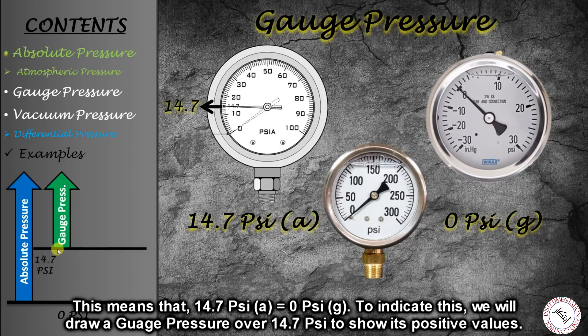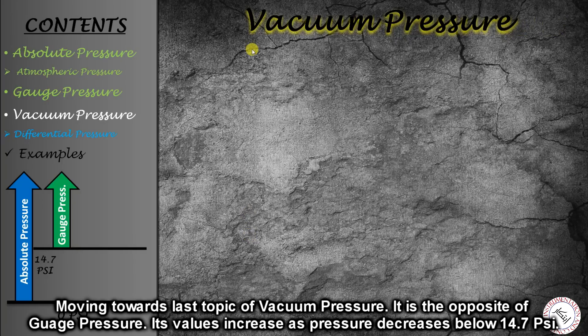If we draw a comparison graph, gauge pressure starts from 0 psi at the 14.7 psi absolute level, and goes in positive values upward. Below 14.7 psi absolute, gauge pressure goes into negative values. Now we introduce the third and last pressure measurement scale: vacuum pressure. Vacuum pressure is totally opposite to gauge pressure — starting from atmospheric pressure at 14.7 psi, as we go down, the value of vacuum pressure increases.